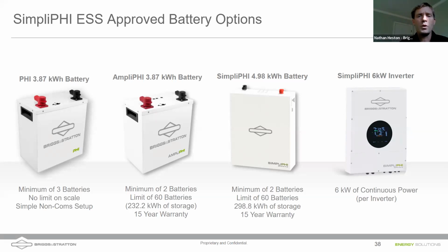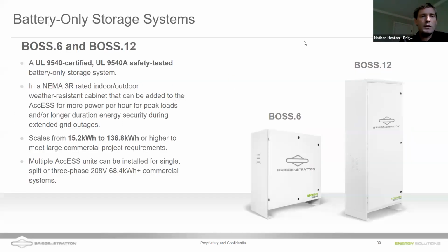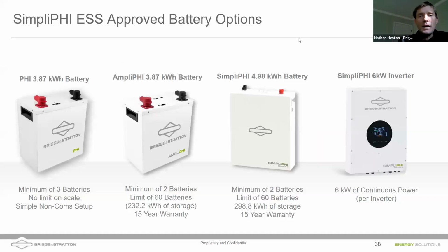There are limitations for the communicating batteries as to how many of them you can put in parallel. You only put our batteries in parallel, never in series, right? So you would never take two 24 volt batteries and try to power 48 volt equipment with them. It would lead to imbalances and loss of warranty and eventually loss of functionality in that battery. So keep that in mind. With the AmpliPHI battery, if you're doing an indoor install, you get a little bit more bang for your buck. It's not a waterproof battery, but for an indoor installation, that battery offers complete communication and temperature control as well.